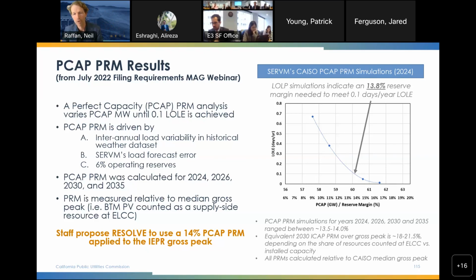The arrow points to the level of resources that leads us to a portfolio with a 0.1 loss of load expectation, our target level of reliability. That's approximately 14% of perfect capacity above the gross peak.